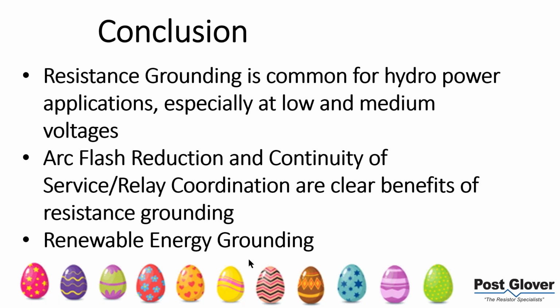Renewable energy grounding. You know, I guess the bottom line is you want to prioritize what's the most important to you. Is continuity of service most important to you? Is arc flash reduction most important to you? Or is it working with the utility? I know of several utilities that already have overvoltage protection, so you're not required to use effective grounding. I think it's unfortunate that some utilities require that. At the same time, I can't blame them; they're protecting themselves in probably the easiest way possible. But that's the point. When you talk about renewable energy grounding, you're going to go with the type of grounding first, and then work your way backwards.